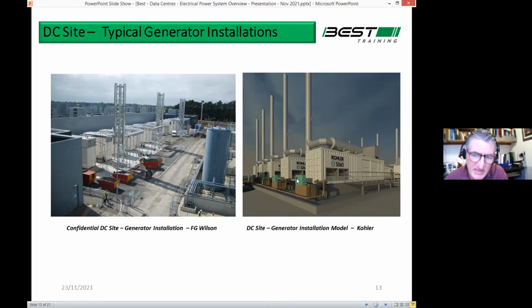Then you also have what they call a fuel polishing system there, because the fuel has to be kept healthy. What happens in tanks is you get condensation of water, and it leads to microbial growth in the fuel, and it just turns into sludge at the bottom of the tank. Then your generator starts sucking up the sludge and blocks the filters in the generator. So to avoid that, you put in a fuel polishing system, and it gets rid of all that sludge so it doesn't cause engine failure later on.